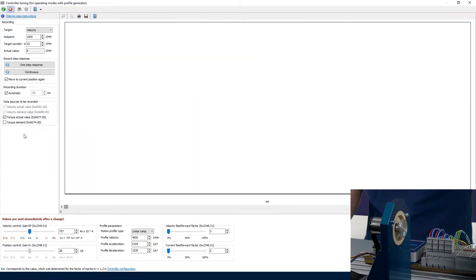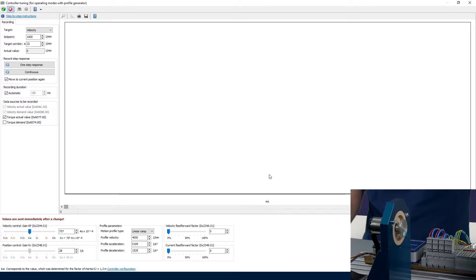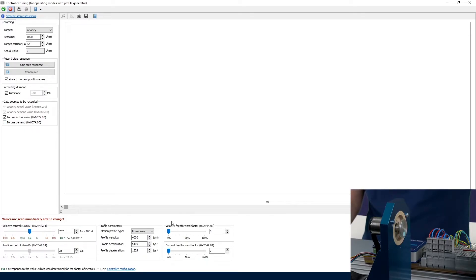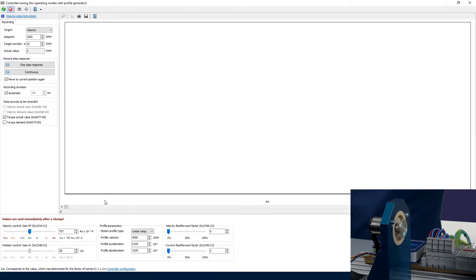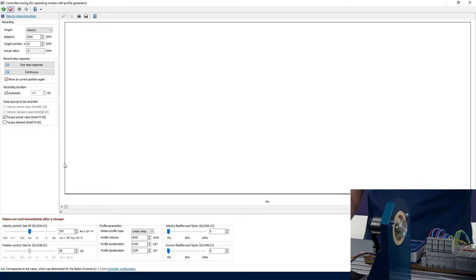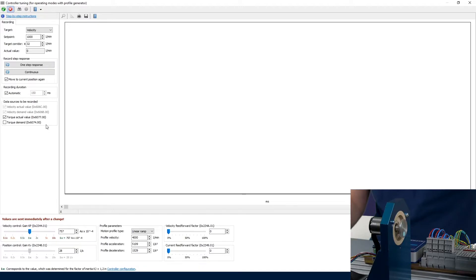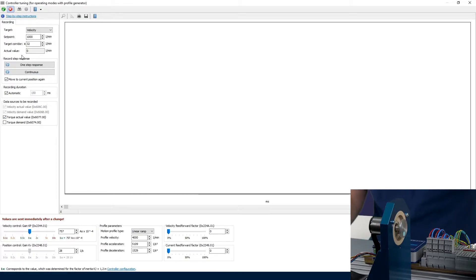Tuning then is done using the controller tuning window. That's a complete set of tools here where the biggest part here is now empty, but that's where we're going to see the actual position and actual speed and so on. On the left side here is the targets and down here are the parameters that we can change in that case. We are starting with the velocity loop because as I mentioned, we don't have to deal with the current loop because these parameters are known by selecting the correct motor. Usually such a step in tuning the speed loop should be somewhere in the middle range of what the motor is capable of. This one would be capable of moving up to 4500 rpm at nominal conditions, but I selected a value of only 1000 rpm here for ease of interpretation.